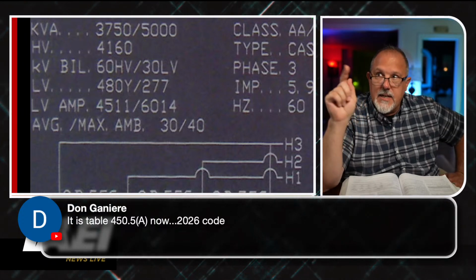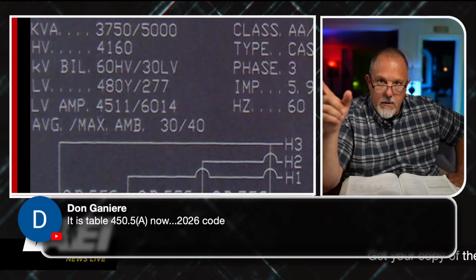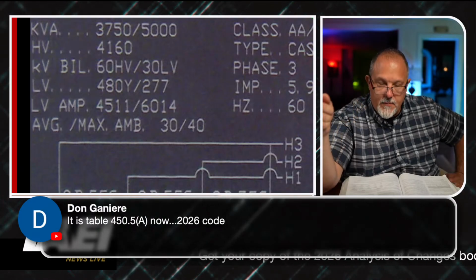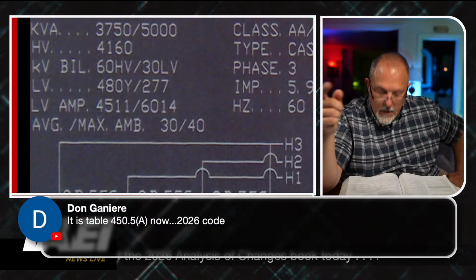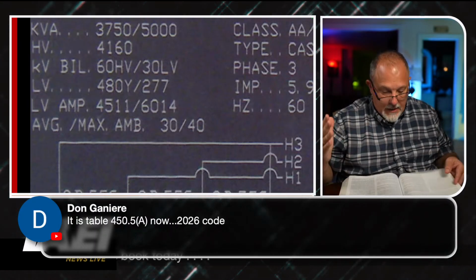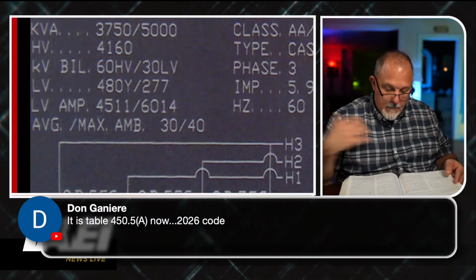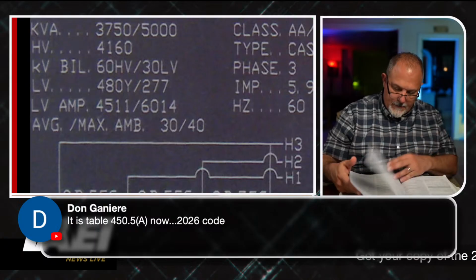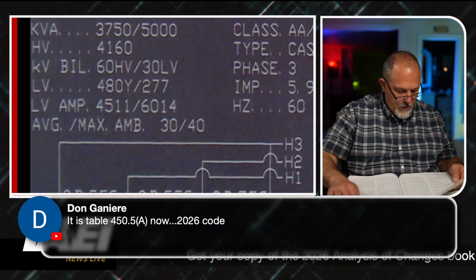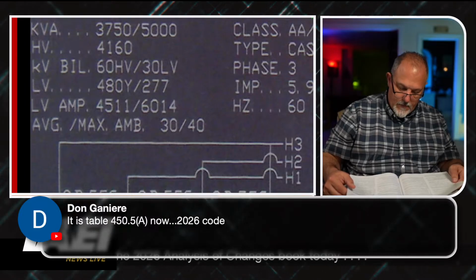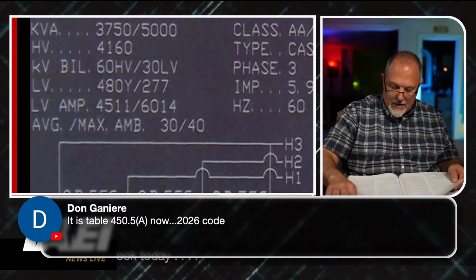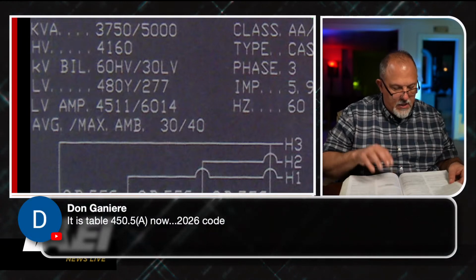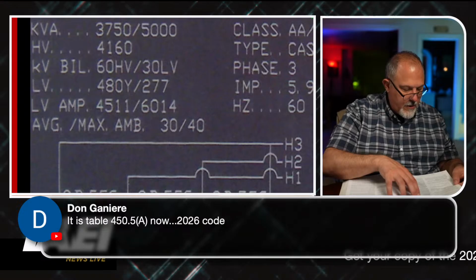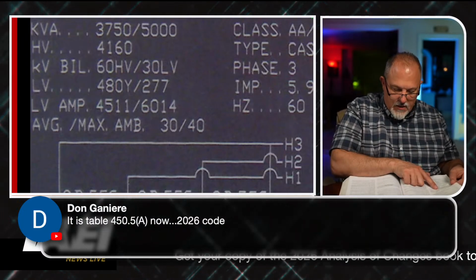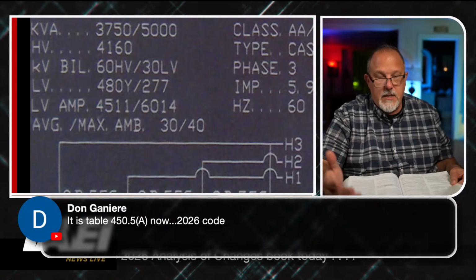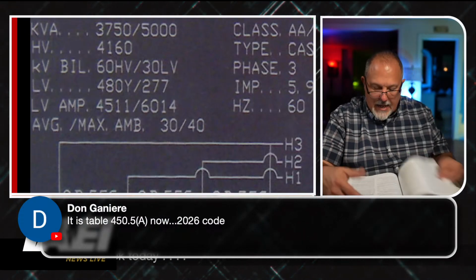There's nothing in the NEC that says I have to accommodate that 5,000, even if I have the potential of putting fans. And I would love to know if you guys think that we should. My gut's telling me, and I'm just trying to see if there's, installation over 35,000 volts. There's nothing in here that speaks to it, they speak to transformer volts. They have oil insulated transformers outdoors, and that's basically dealing with the oil insulation. But there's nothing here about fans.